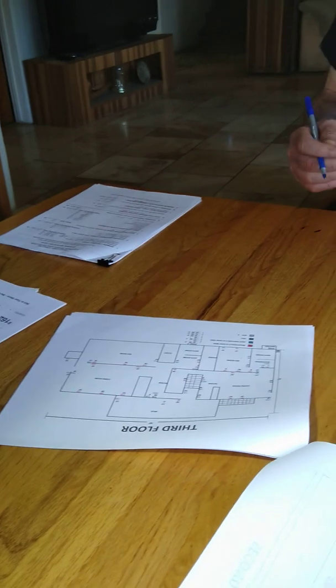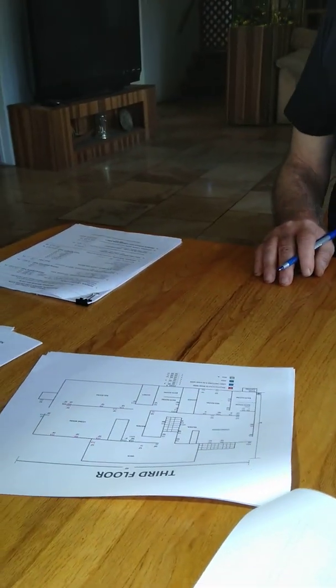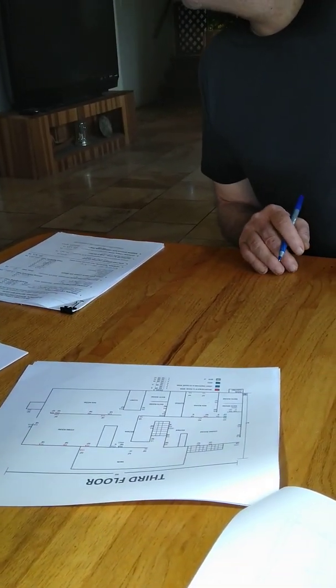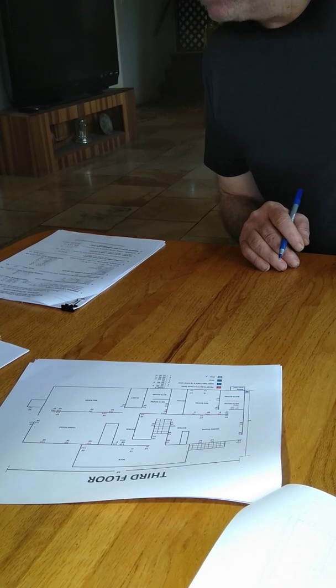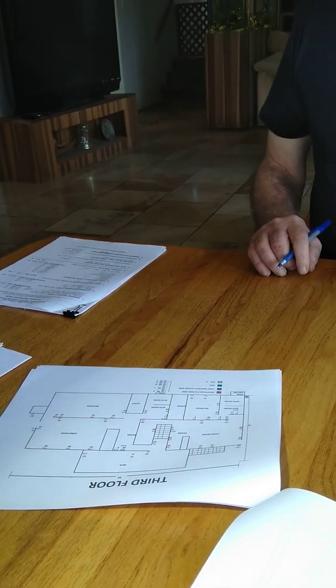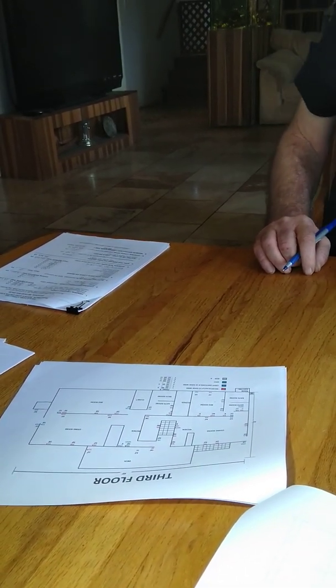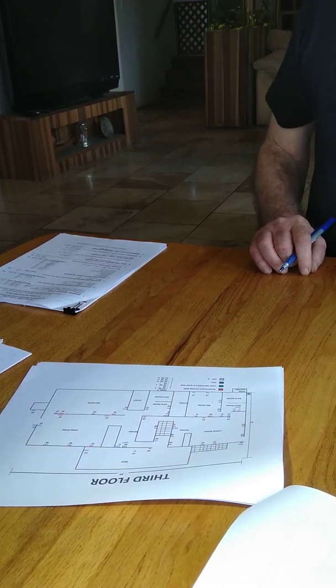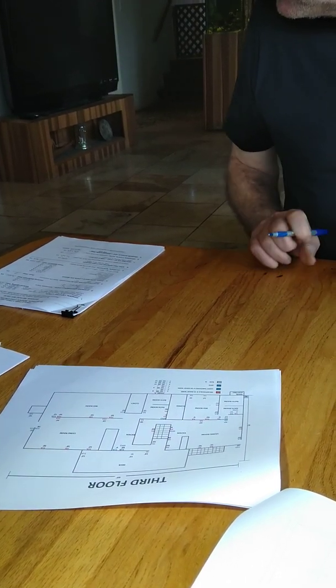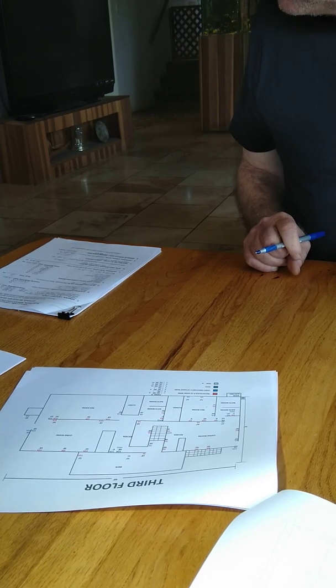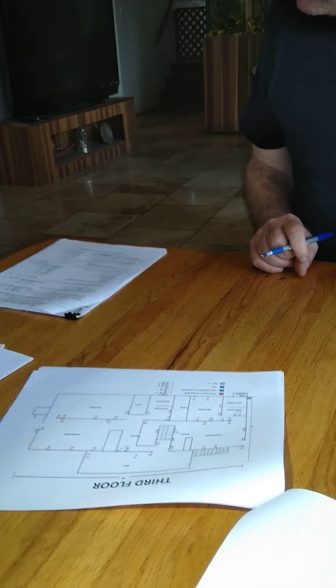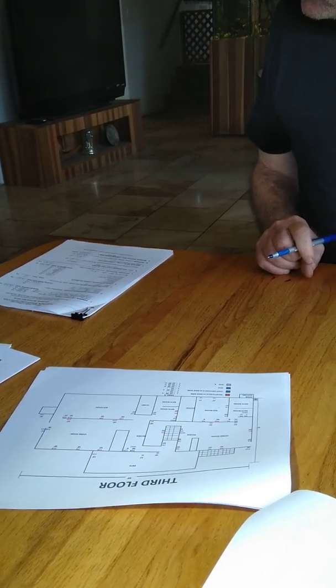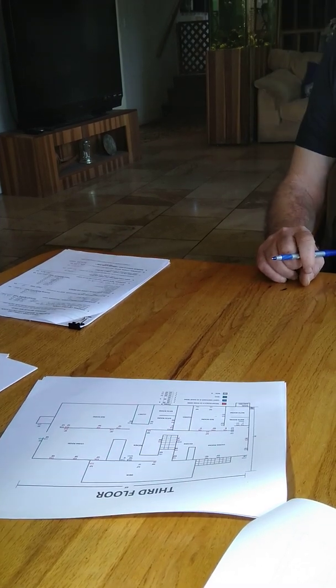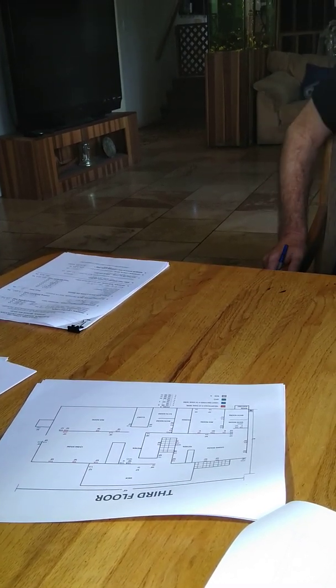It sounds like the 8 gauge would do the job, predicated on the size of the circuit breaker that's required for that 2 horsepower pump. So you have to figure out your circuit breaker. It could be a 40 amp. A lot of these pumps are 40 amps. So with a 40 amp, you might find that number 8. I'd have to go back and look at the table, and I believe the number 8 is for 40 amps.